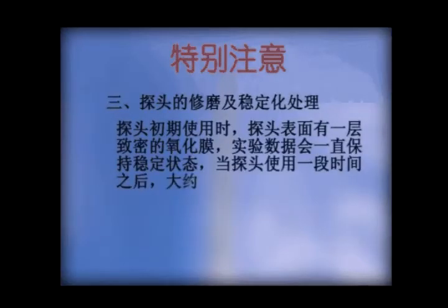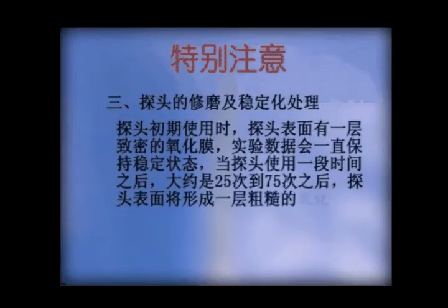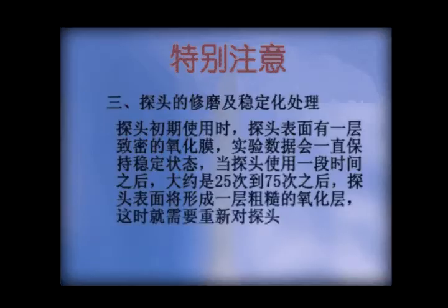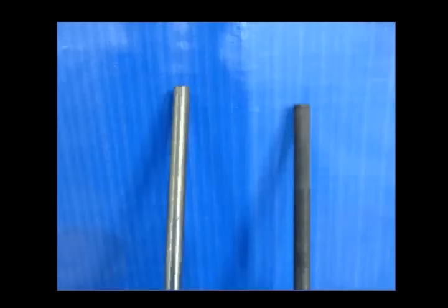Special remarks 3. Grinding and stabilizing treatment of the probe. In early use, the probe surface has a layer of dense oxide film, and the experimental data will remain stable. When the probe has been used for some time, about 25 to 75 tests, a rough surface oxide layer will form, and the probe will need to be repolished. The order and method of grinding is as follows.